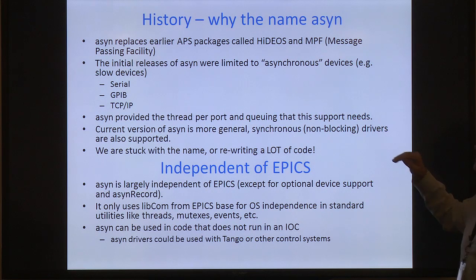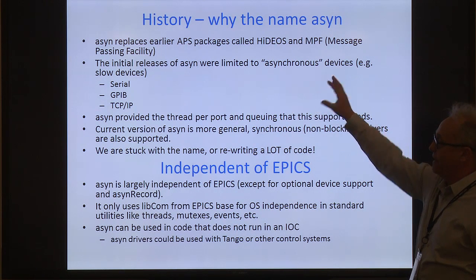So his initial concept of asyn was limited to asynchronous devices. In other words, slow devices, where in EPICS, when a record is processing, it must not block. The record processing and calling device support must happen as quickly as possible. So you cannot wait for any communications with a slow device. So that means that the driver that you're using for that needs to run in its own thread, and EPICS needs to basically start an I/O operation and then get notified when the I/O operation completes. So that was his basic goal for writing asyn.